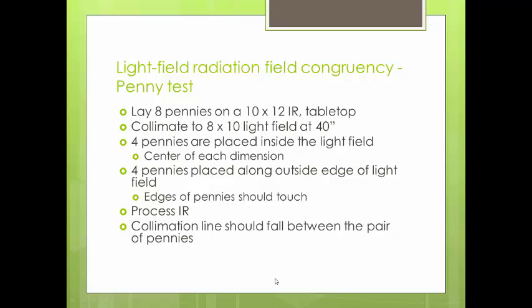Today's quality control lecture is going to be on light field radiation field congruency — the eight penny test. Light field radiation field congruency tells us that our light field that we see is also the same as the radiation field that we are exposing.